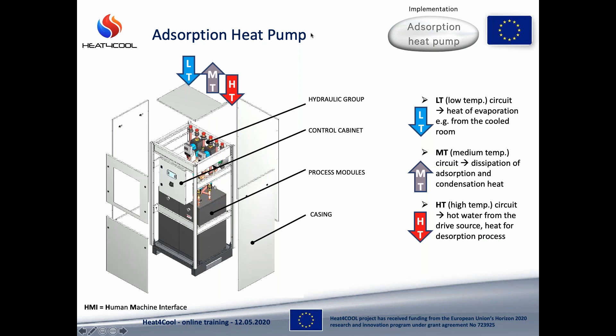The main components of our adsorption heat pumps are the process modules — always an even number: two, four, six, or eight. There is also a hydraulic group consisting of pumps and three-way valves directing the HTF at the right temperature levels to corresponding heat exchangers, a control cabinet with human-machine interface, and casement with frames. At the top you can see the connections of the three circuits: LT has to be connected to the cold distribution circuits, for example fan coils.